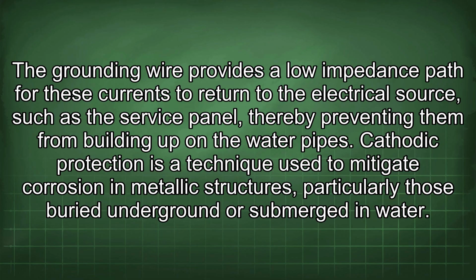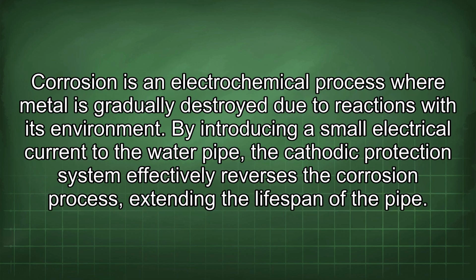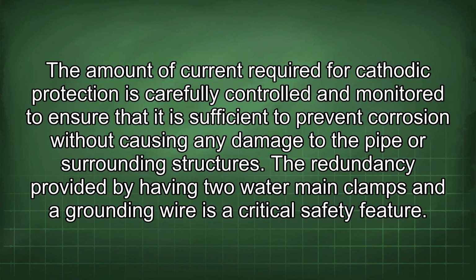Cathodic protection is a technique used to mitigate corrosion in metallic structures, particularly those buried underground or submerged in water. Corrosion is an electrochemical process where metal is gradually destroyed due to reactions with its environment. By introducing a small electrical current to the water pipe, the cathodic protection system effectively reverses the corrosion process, extending the lifespan of the pipe. The amount of current required for cathodic protection is carefully controlled and monitored to ensure that it is sufficient to prevent corrosion without causing any damage to the pipe or surrounding structures.